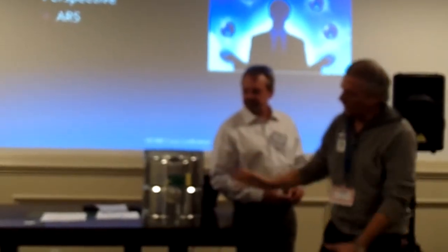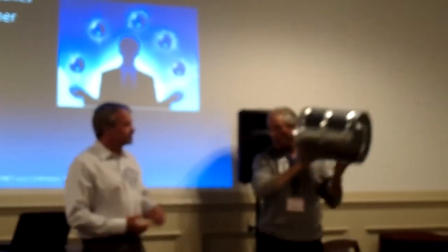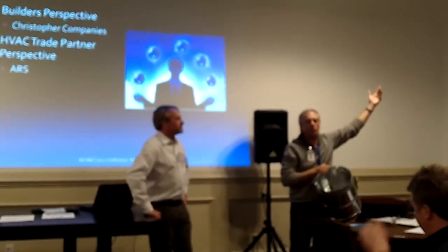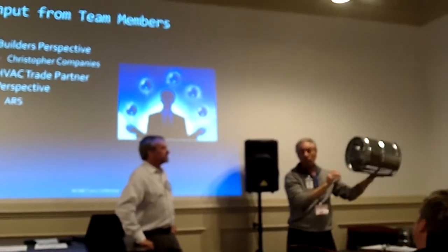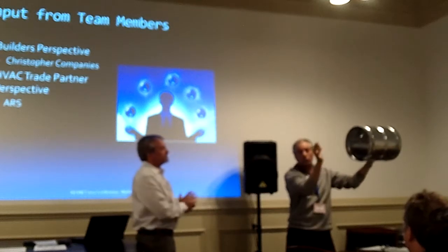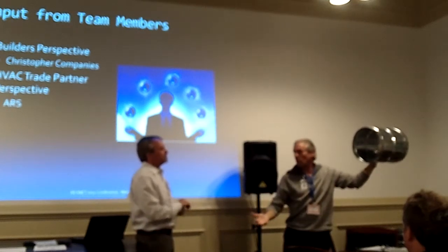Now that you've got this range hood, per the 2009 code, if you're going to exhaust a 12-inch round, you now have to have another 12-inch round somewhere in the ceiling or wherever you put it, so that when the range hood turns on, this damper opens. I don't care if it's 17 degrees outside or 95 degrees outside, this isn't tempered air. It's whatever the temperature is outside that you're bringing inside.